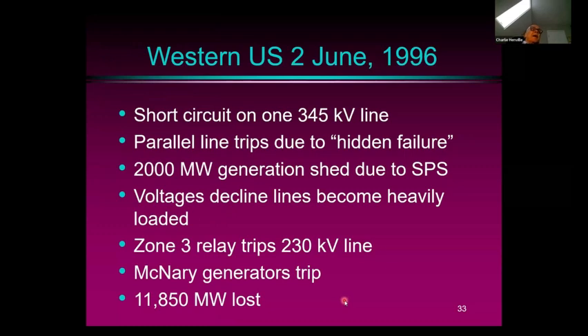In the case of the Western states in the United States, in 1996, there were a few severe blackouts. In this one I'm describing here, there was a short circuit on one 345 kV line, and the parallel line also tripped out unexpectedly due to a hidden failure. And there was 2,000 megawatts of generation lost. There was what's called a special protection scheme, which deliberately tripped the generation offline because of the sudden loss of these two transmission lines.